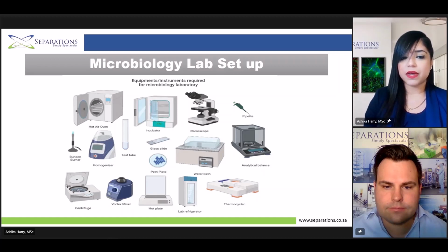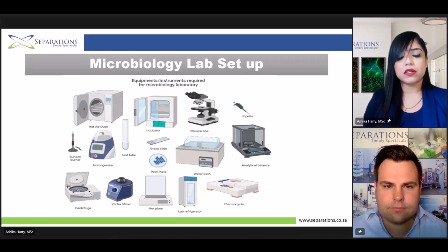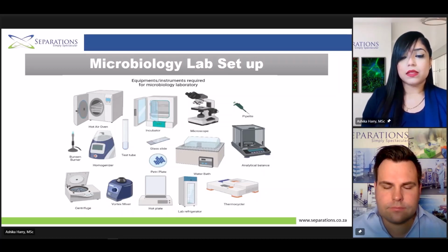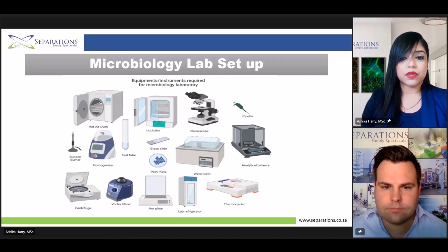For culture and identification in the microbiology lab, typical instruments you would require would be an analytical balance. So this is used to measure the mass of your granules or your powders or your liquids. Then the most important one would be your microbiological safety cabinet, which we just mentioned and saw in the previous slide. So in a microbiology lab, you are typically working with potentially hazardous or infectious microorganisms and also hazardous chemicals. And this could pose a risk to the personnel handling this or also the environment. So what's needed is a safe environment to work in that can also be contamination free.